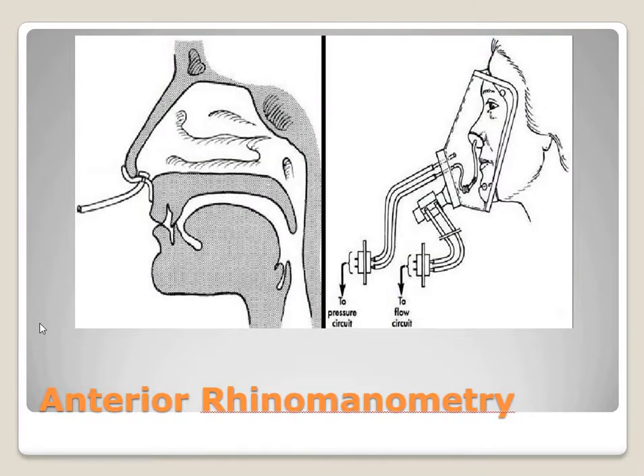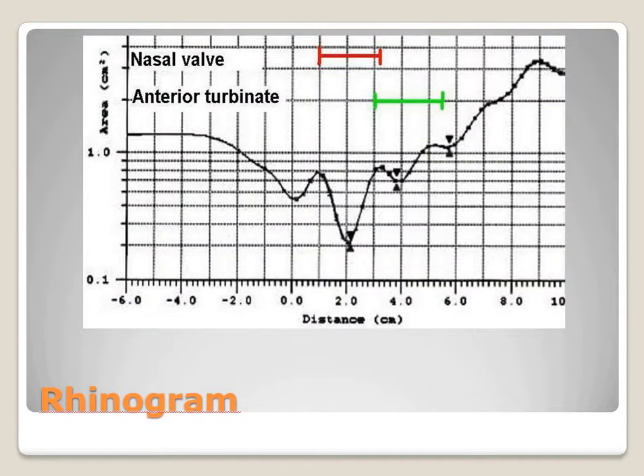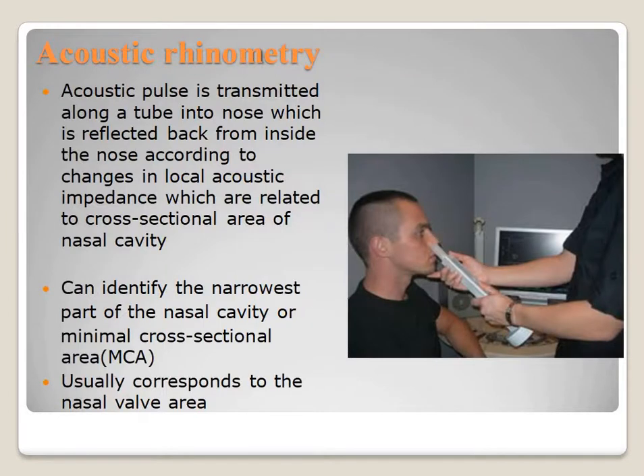Here we can see the placement for anterior rhinomanometry according to the location of the sensing tube. In acoustic rhinometry, an acoustic pulse is transmitted along a tube into the nose and reflected back from inside the nose according to changes in local acoustic impedance, which are related to the cross-sectional area of the nasal cavity. It can identify the narrowest part of the nasal cavity — the minimal cross-sectional area — which usually corresponds to the nasal valve area.